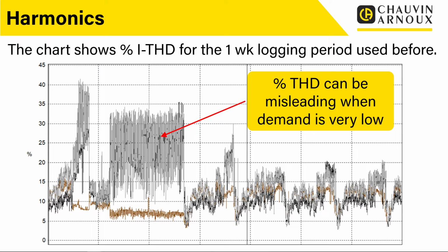The other thing to be aware of is that a lot of times when you've got things like power supplies operating at low load, at a small percentage of their capacity, they're almost just ticking over. That's where a lot of the harmonics are generated, because the power supply is trying to chop that waveform down, because it knows it doesn't need much power. So there's a lot more switching going on in that case. So sometimes when things have a low load, they can produce a lot more harmonics. And actually, if you turned on a few more loads and loaded things up, the harmonics would decrease quite significantly.